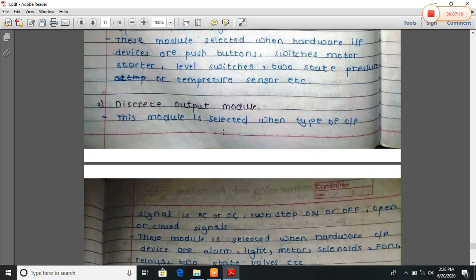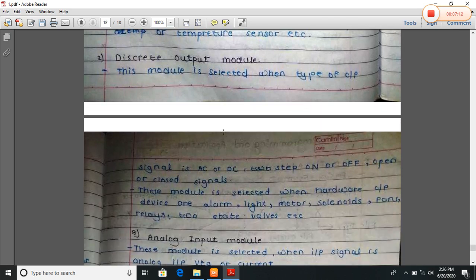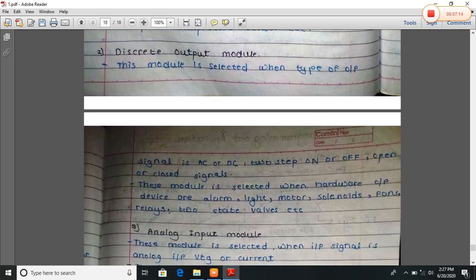Discrete output module: this module is selected when the type of output signal is AC or DC, two-state on/off or open/close signal. This module is selected when hardware output devices are alarms, lights, motors, solenoid valves, fans, relays, two-state valves, etc.